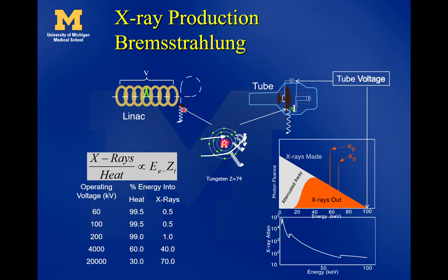What the target is made out of is important. We need something higher in atomic number — like tungsten, copper, or some other metal — and something that can get hot without melting. A lot of times these targets are made out of tungsten, which has a high melting temperature, or copper, which contributes to production efficiency.